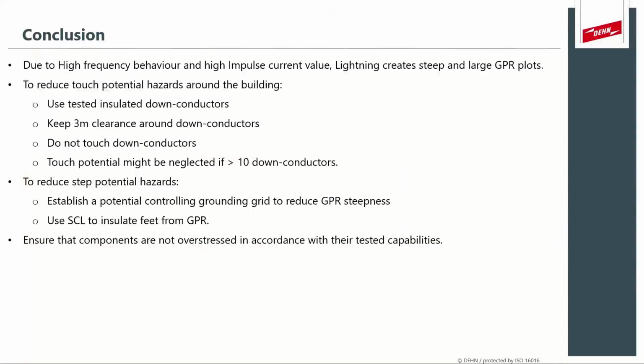Okay, so just to take a step back and conclude and recap on everything that we spoke of. Due to the high frequency behavior and the high current values, fault current, impulse current values that lightning creates, it creates extremely steep and large ground potential rise plots. Now, to reduce the touch potential hazards around a building to fight against this ground potential rise, we use tested insulated down conductors or keep a 3-meter clearance distance around the down conductors. Put up signage to say that people should not touch the down conductors.